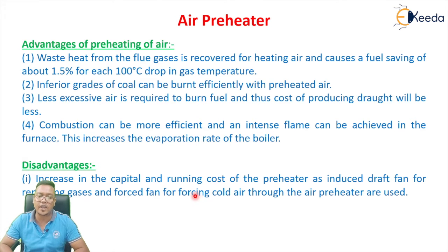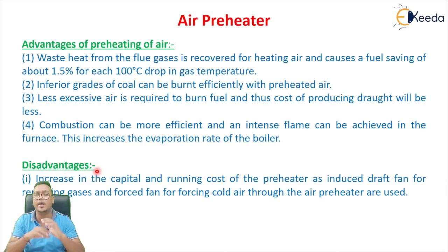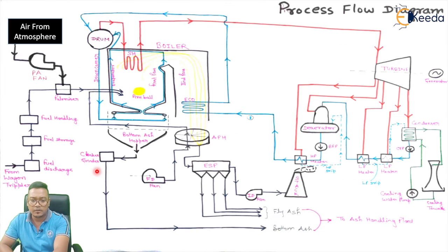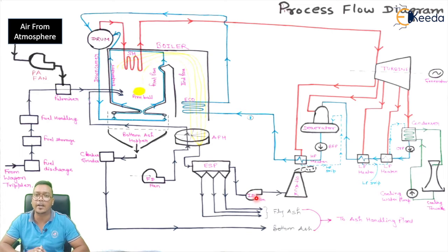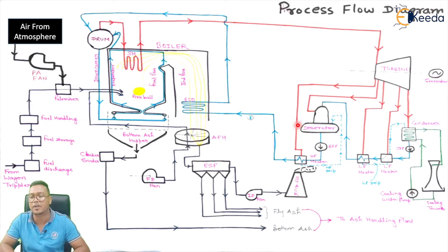The disadvantage of the air preheater is the same as for the economizer. During natural draft, the economizer was increasing the pressure drop, and in the same way the air preheater will increase the pressure drop. Because of this pressure drop from both the economizer and air preheater, we need to use an FD fan and ID fan. We use these fans to reduce the pressure loss so that the draft — that is, the pressure difference — can be maintained, allowing flue gas to flow from the boiler to the chimney easily.